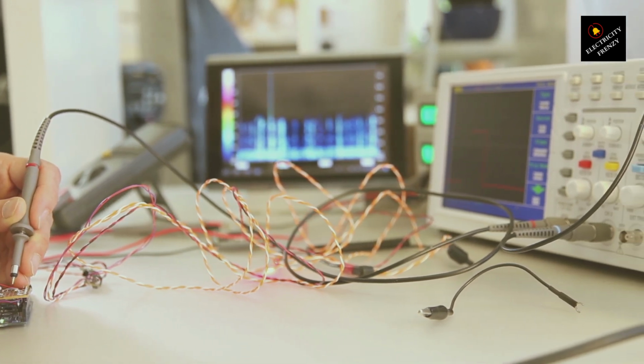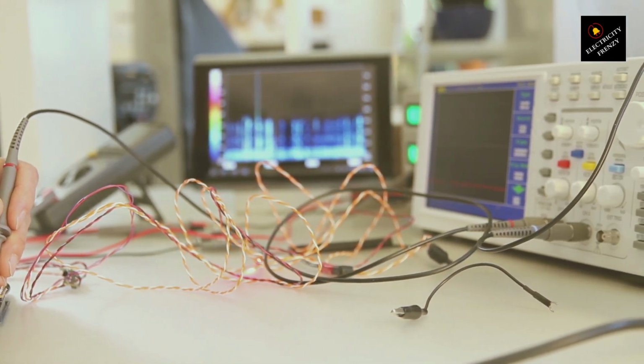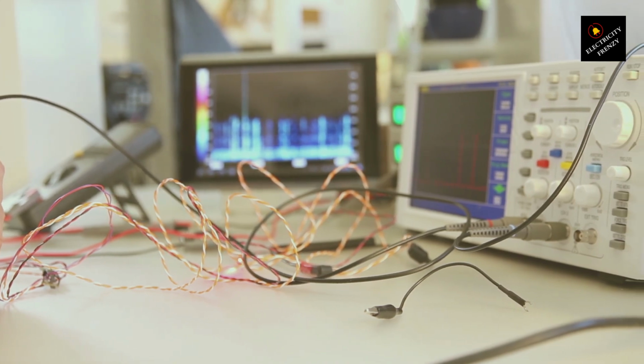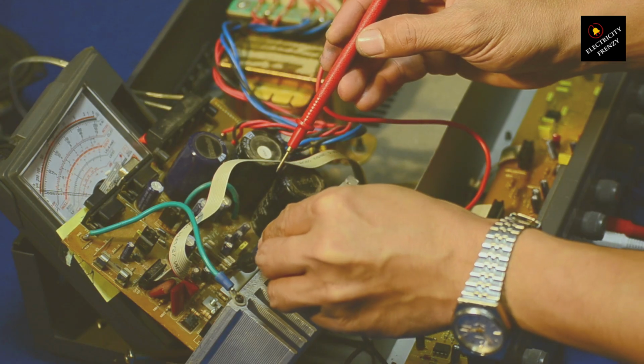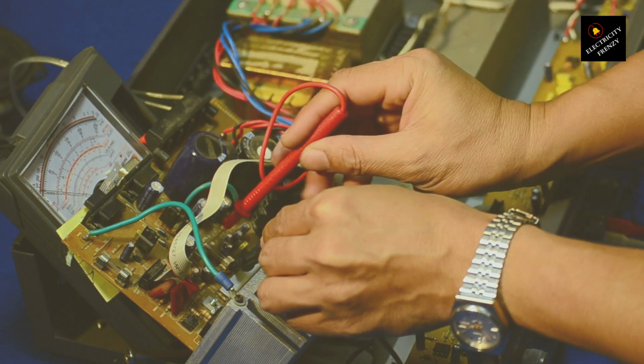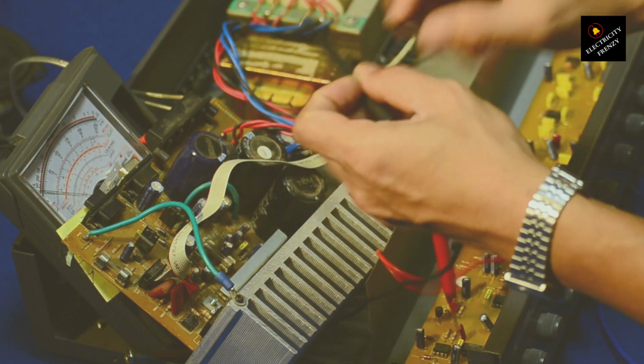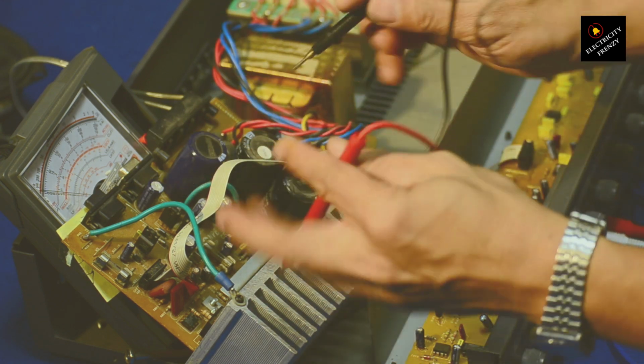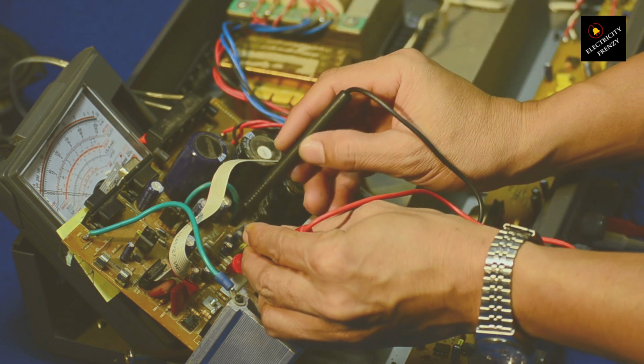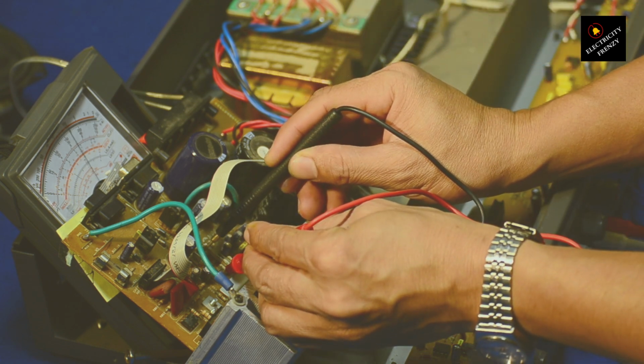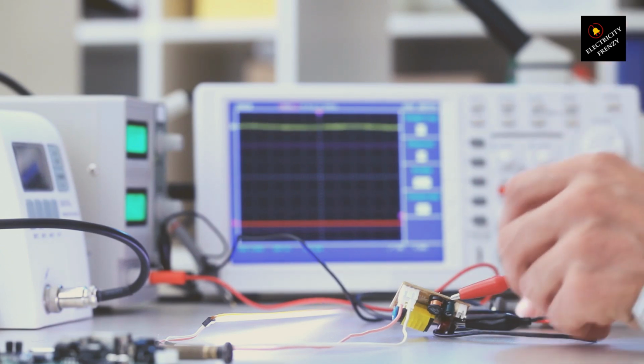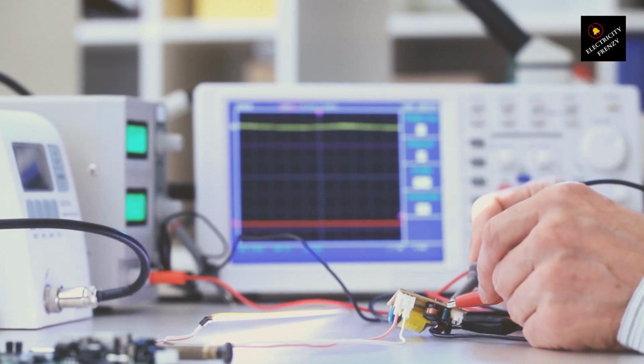It can burn out, not to mention posing a serious fire risk. Think of it like this: your transformer is like a bridge over the 220 volts rapids. If the bridge isn't strong enough to handle the weight crossing over it, it's going to collapse. So making sure your transformer has a higher power rating than your motor is like building a bridge strong enough to handle a fully loaded truck. It ensures that everything flows smoothly from one side to the other, without any breakdowns.